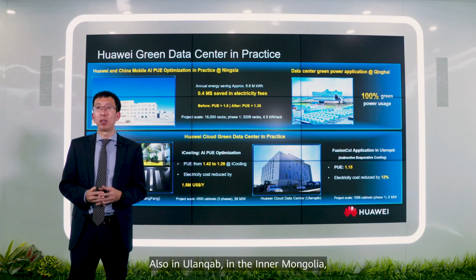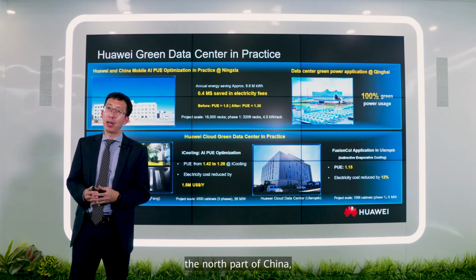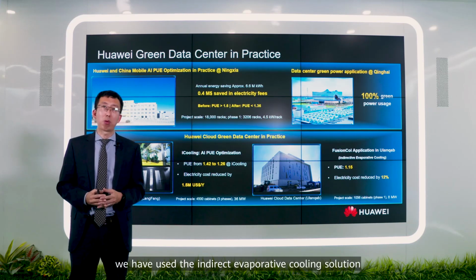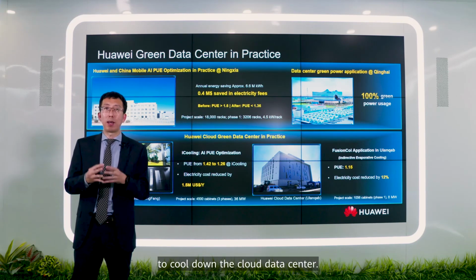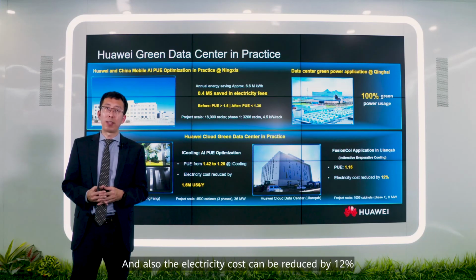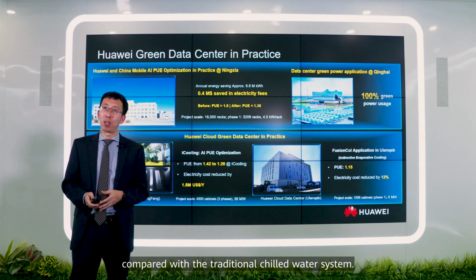Also in Ulanqab, in Inner Mongolia in the north part of China, we used the indirect evaporative cooling solution to cool the cloud data center. The PUE is lower, around 1.15, and electricity cost can be reduced by 12% compared with the traditional chilled water system. We believe that with our contribution and innovative solutions, we can realize a green data center and take responsibility for carbon neutrality.